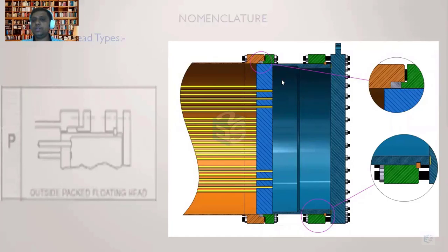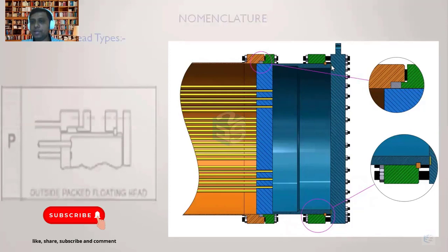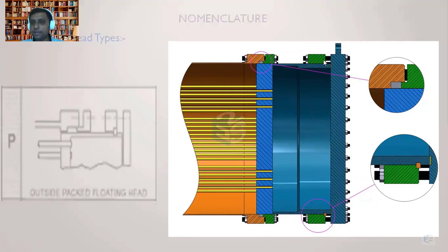Looking at a clearer image: the tube sheet is welded to the channel shell. There is a gasket placed inside the blind cover. This cover is free and movable — when the stud assembly is untightened, the cover can be removed. This cover along with the gasket has to be tightened against the channel shell surface.